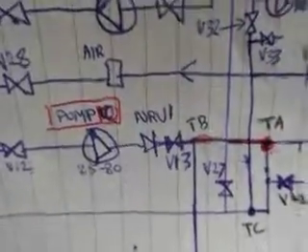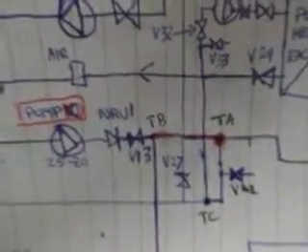So looking at the diagram, we've come in through the filter, V12, pump 10, non-return valve, then the T-piece TB, then through to TA. So if we go to TB, then up along the pipe to TA, there's T-piece TA, and we carry on. Then the flow carries on through T-piece TC. It's connected to the buffer at that point, to TA, and around then along this pipe here, where there's a T off there, which is valved off, and then it just goes down this pipe and back to the house again. Some of the T-pieces that we passed out were the junctions for the pool, basically.